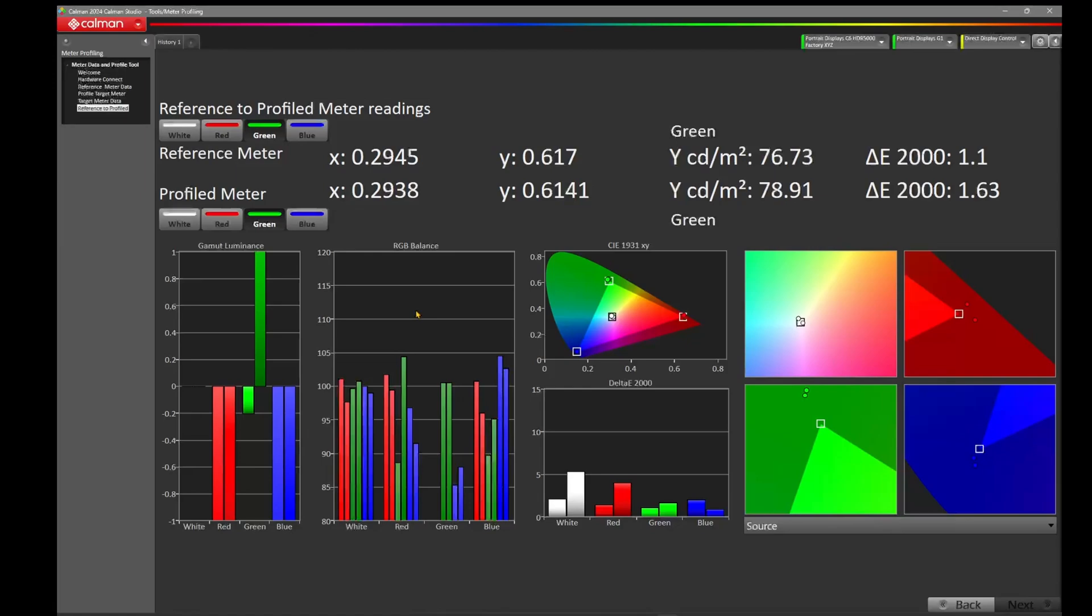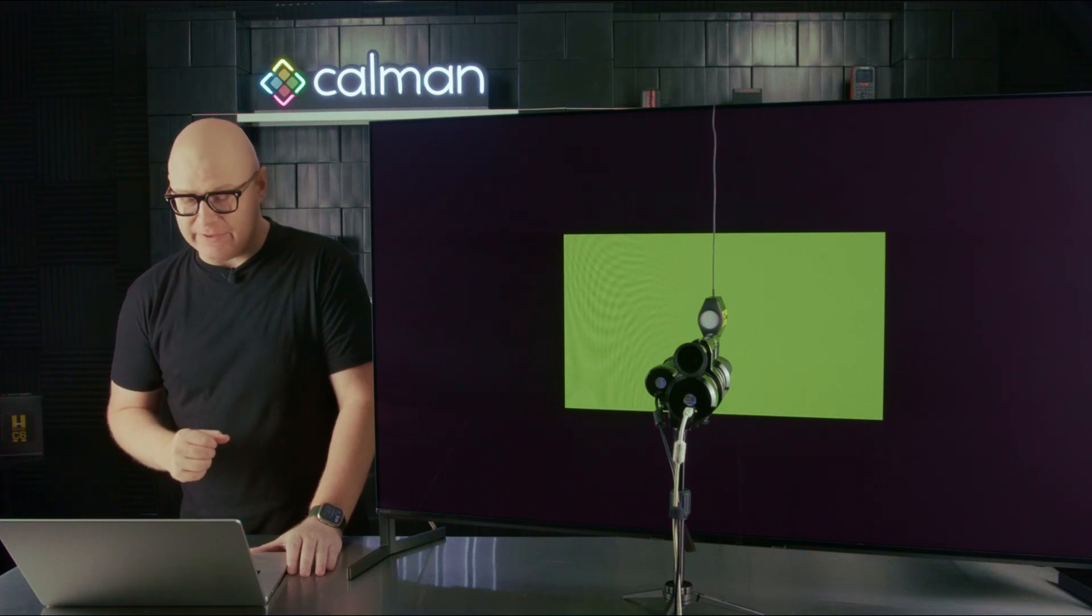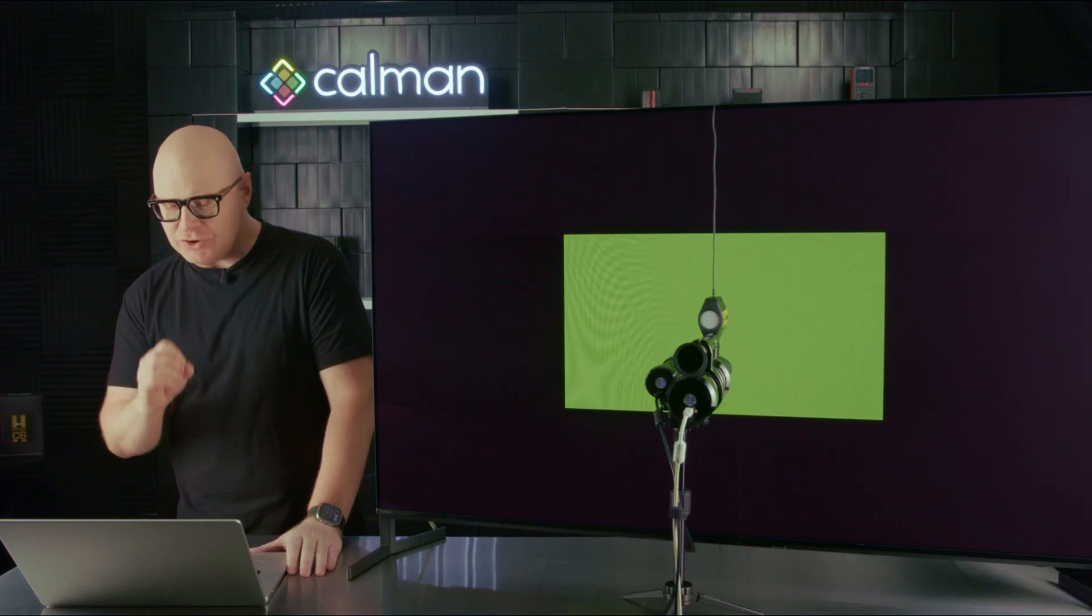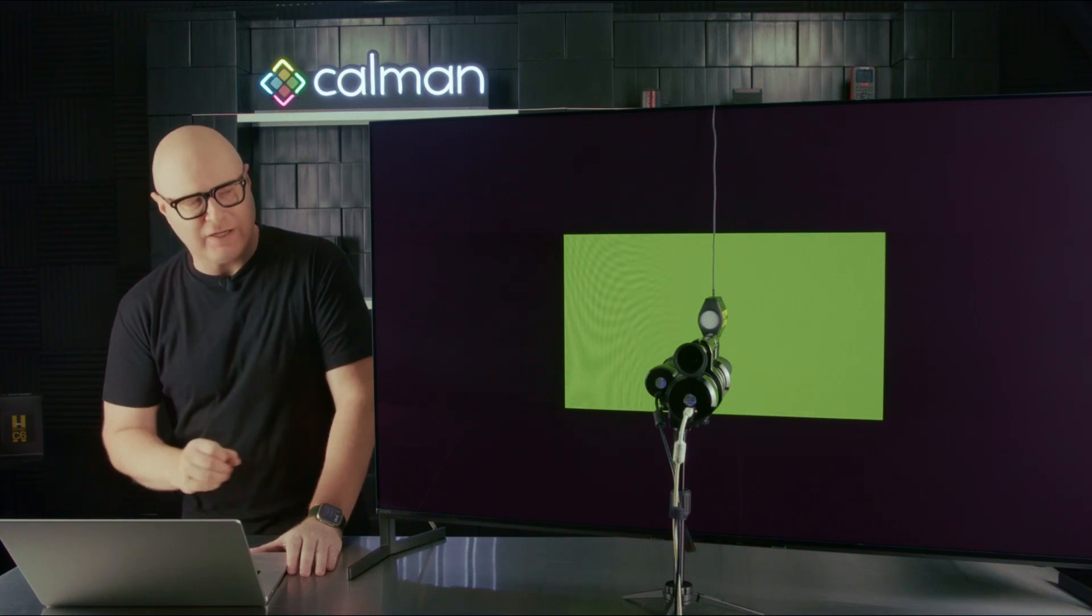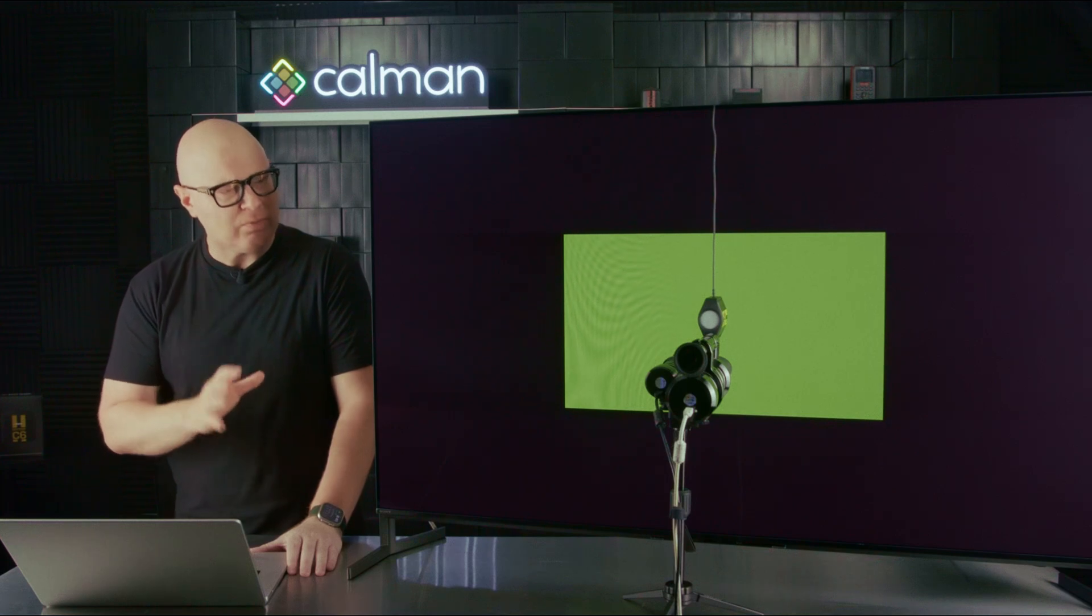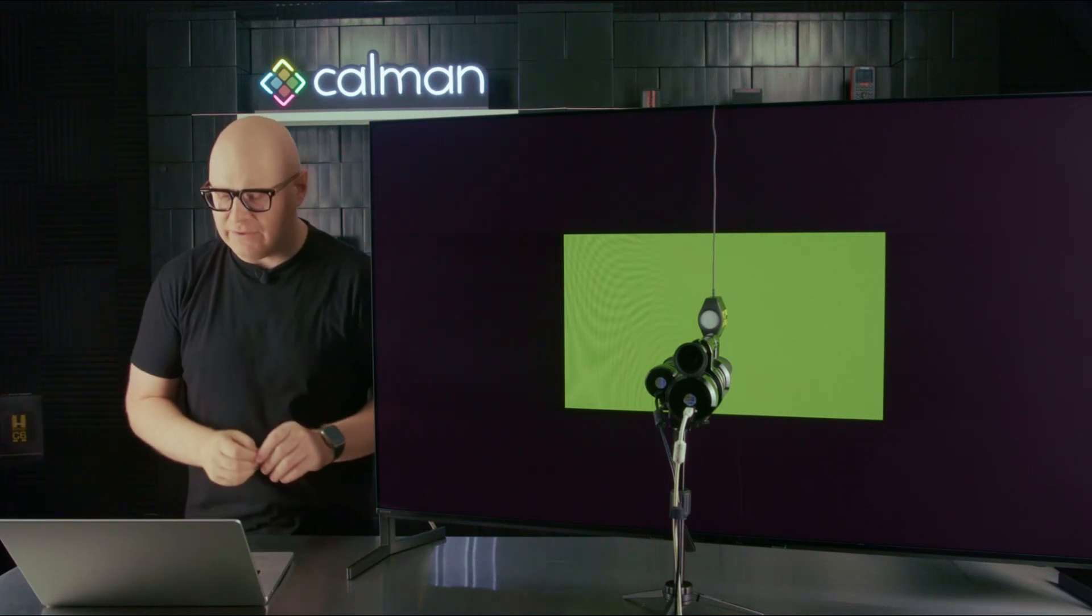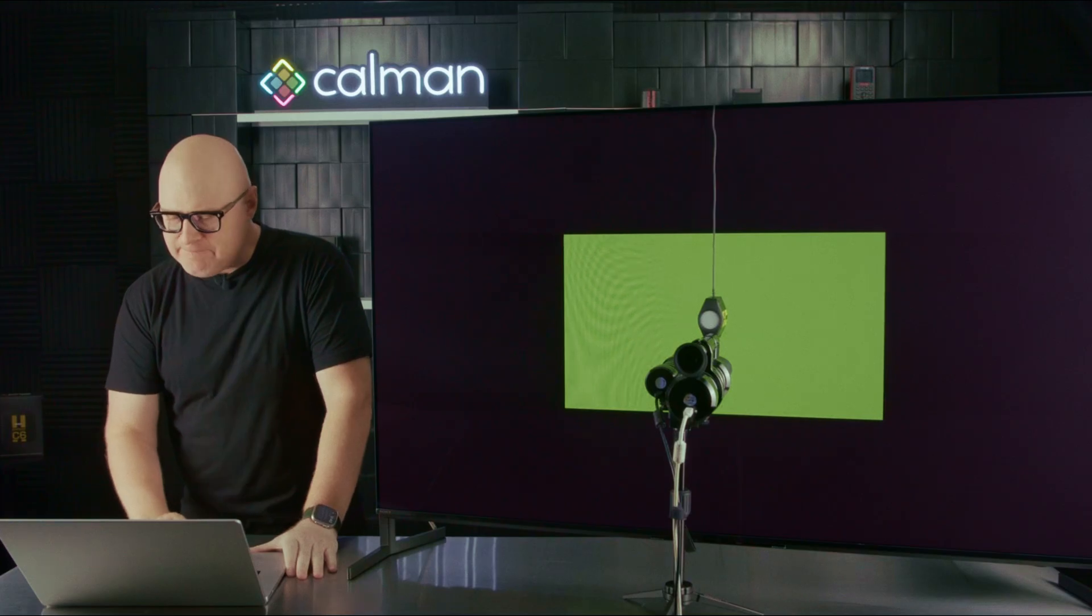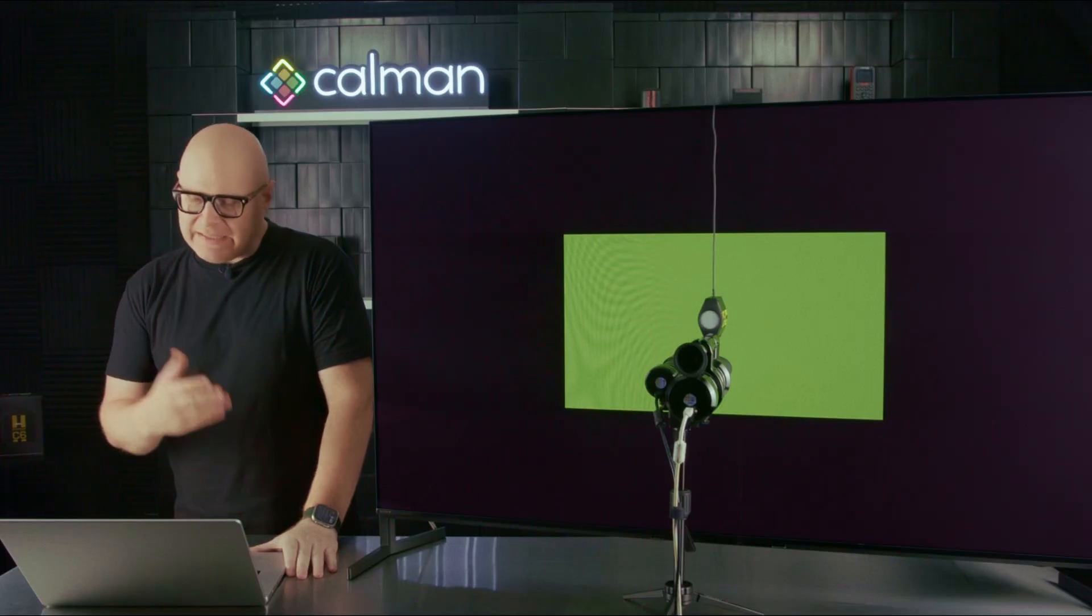Now let's look at red on Y, 0.325, 0.337. Once again, our errors are starting to get pretty large. And let's look at that large Y, 21.7, 22.08. Not too bad there, but we do have some significant errors on the X and Y when you're trying to calibrate to a known target. Let's look at green. Here we are on the X, 0.2945, 0.2938. Not too bad on the green there with X. Y, 0.617, 0.6141. Not too bad there. We're still pretty much at that tolerance. We're just outside that at 0.0031, so we're pretty close. Again, we have lights in the room, some variabilities here. And then let's look at our green Y, 76.73, 78.91. We're about two nits off.